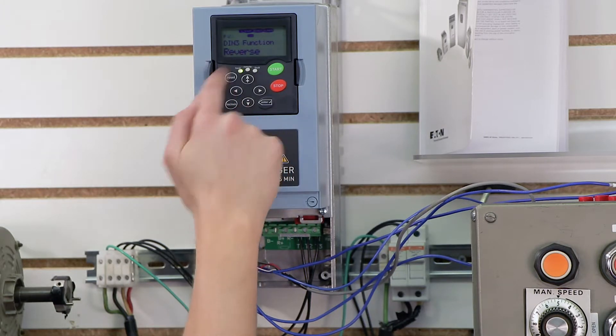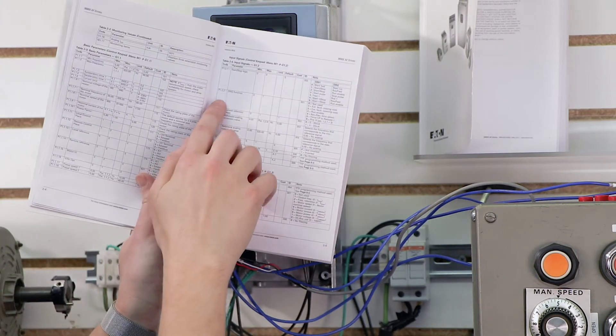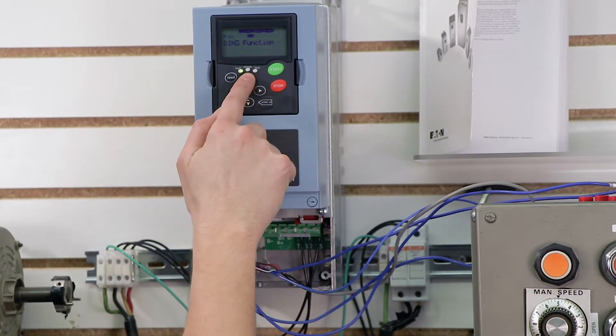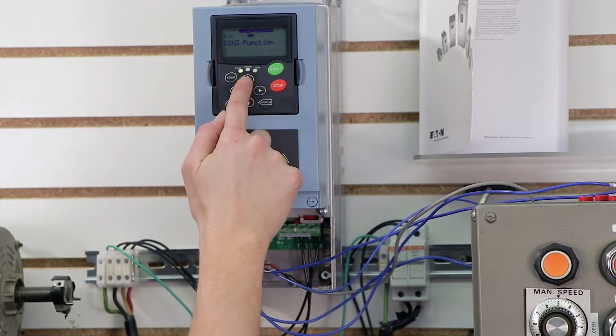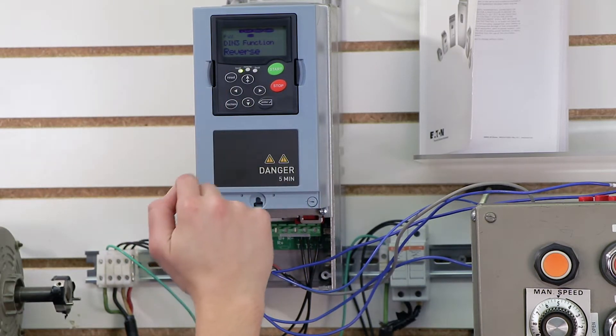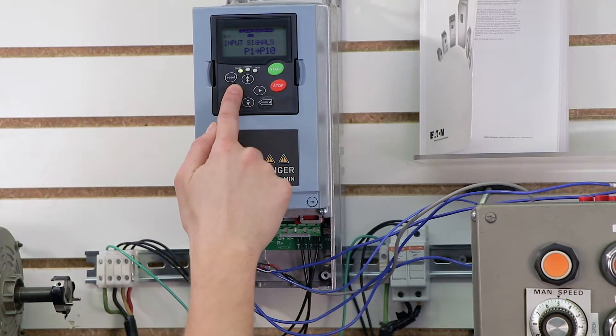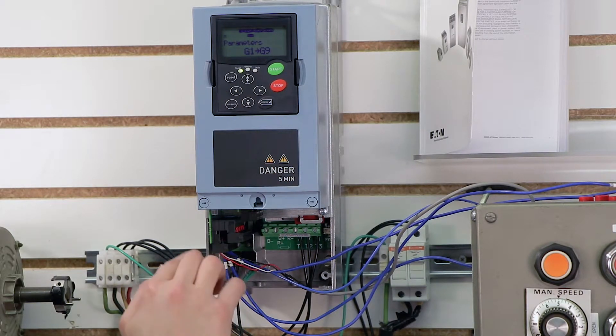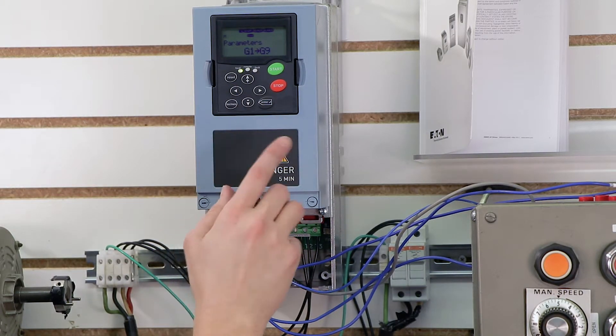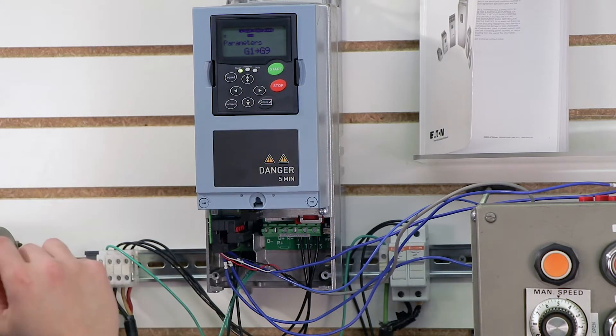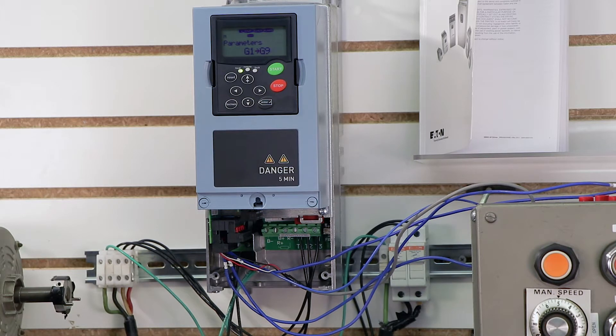Now I'm going to go to 1.2.2, which is our digital input 3. I'm going to press right again, and I'm going to scroll up through these until I find my reverse function, which is right here, and I'm going to press enter. And that is it for programming. I've set up both my digital inputs for start and stop, my first two digital inputs, and then I also set up my third digital input for my forward reverse on the selector switch. So let's go ahead and test it.